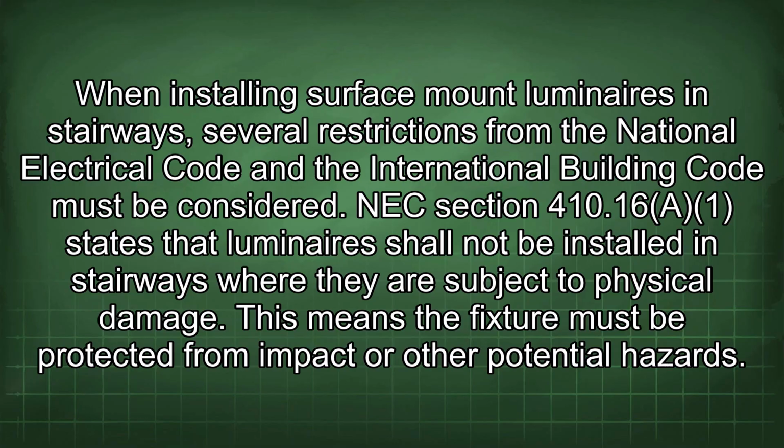When installing surface mount luminaires in stairways, several restrictions from the National Electrical Code and the International Building Code must be considered. NEC Section 410.16(A)(1) states that luminaires shall not be installed in stairways where they are subject to physical damage. This means the fixture must be protected from impact or other potential hazards.